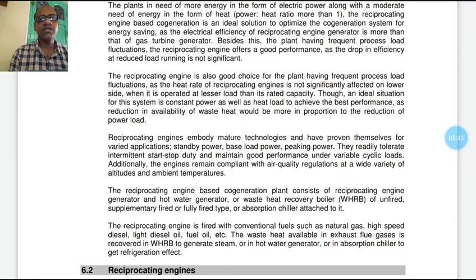The reciprocating engine based cogeneration plant consists of a reciprocating engine generator and a hot water generator or waste heat recovery boiler of unfired, supplementary fired or fully fired type, or an absorption chiller attached to it. The reciprocating engine is fired with conventional fuel such as natural gas, high speed diesel, light diesel oil, fuel oil, etc. The waste heat available in exhaust flue gases is recovered in a waste heat recovery boiler to generate steam, or in hot water generation, or in an absorption chiller to get refrigeration effect.